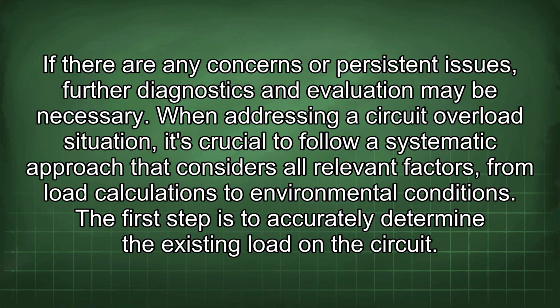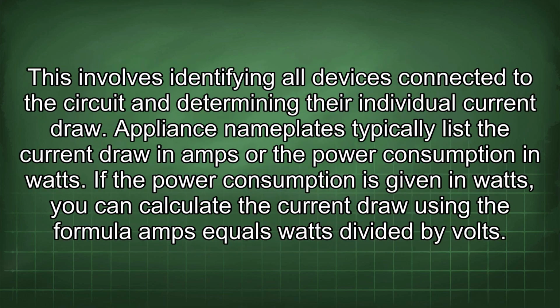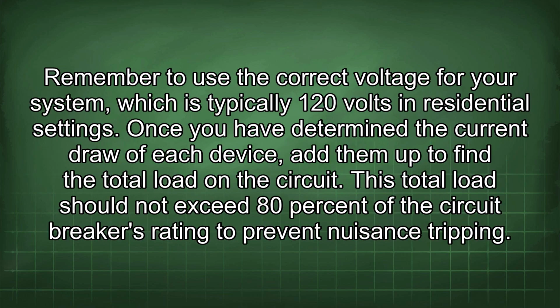When addressing a circuit overload situation, it's crucial to follow a systematic approach that considers all relevant factors from load calculations to environmental conditions. The first step is to accurately determine the existing load on the circuit. This involves identifying all devices connected to the circuit and determining their individual current draw. Appliance nameplates typically list the current draw in amps or the power consumption in watts. If the power consumption is given in watts, you can calculate the current draw using the formula amps equals watts divided by volts. Remember to use the correct voltage for your system, which is typically 120 volts in residential settings.